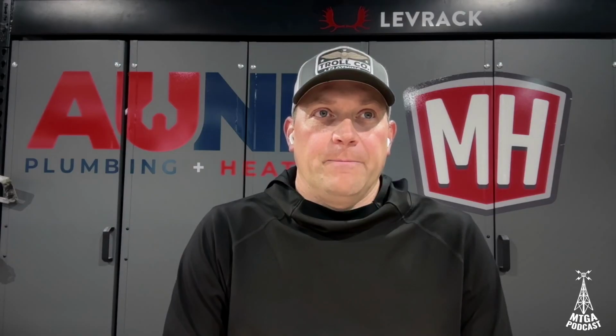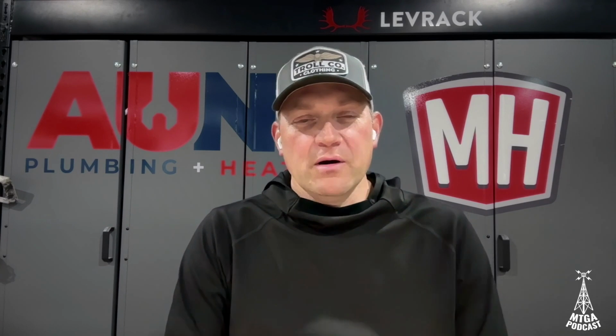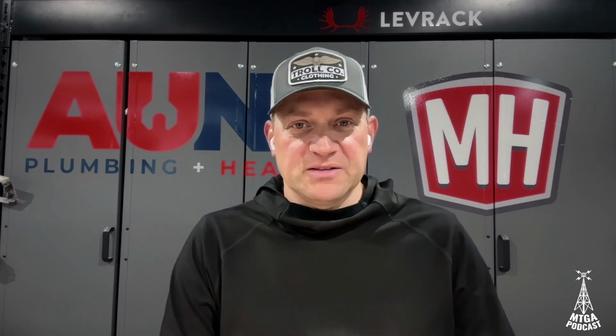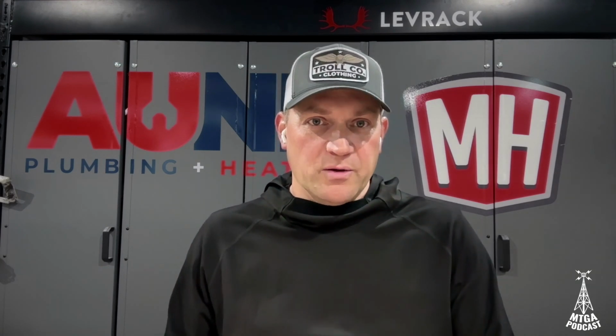So, you and I did the 5 ton unit here this week. Earlier in the last week, my crew and I did the little 1.5 ton unit, and I was blown away how fast that thing recovered a 40-gallon indirect. Part of it is that it's got the loop pump built into the indoor unit. So we've got this monoblock outside unit, with a supply and return pipe coming from that unit into the indoor unit that's on the wall.